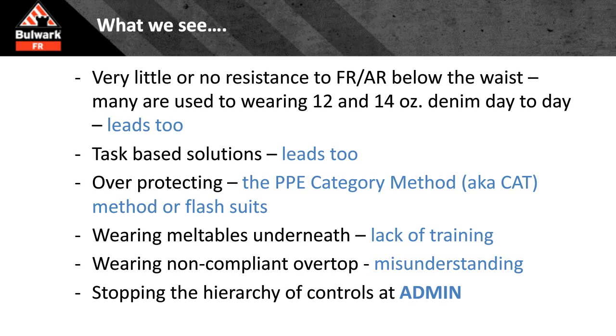So what does that tend to lead to from the waist up? It goes back to the mindset of, just put it on when you need it. That's a task-based solution, but the problem with task-based thinking is it tends to lead to overprotecting, to an NFPA 70E table mentality, a simplified two-step approach, or just donning a flash suit. But there's no need to don a flash suit for a 12-calorie job when your only options are 25 or 40 calorie flash suits.